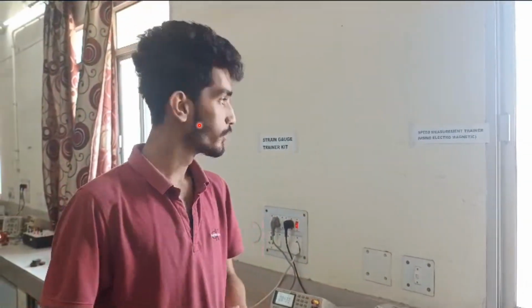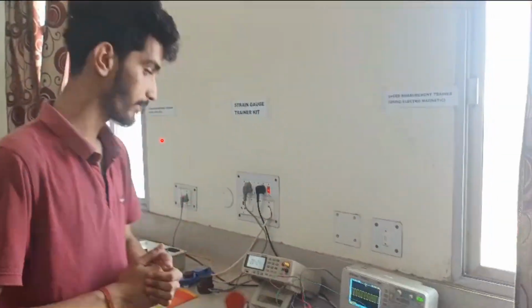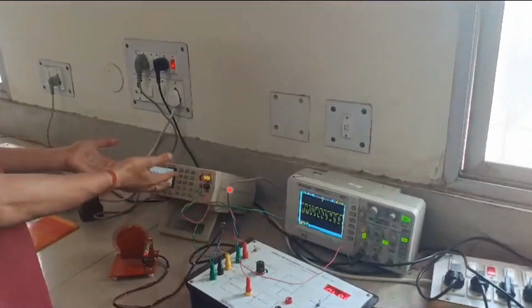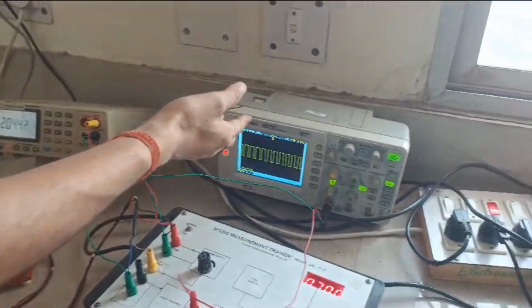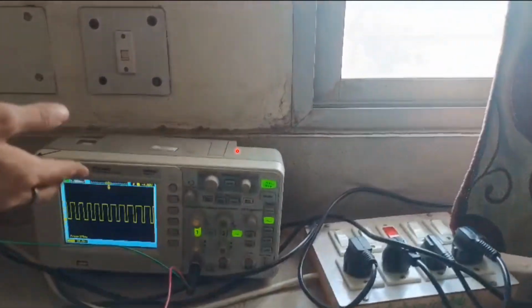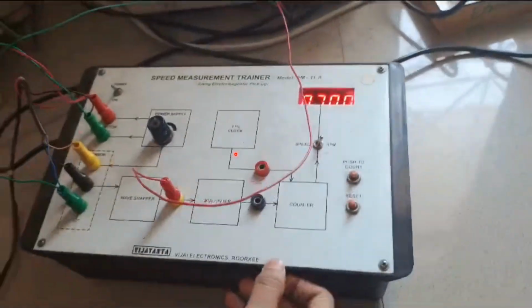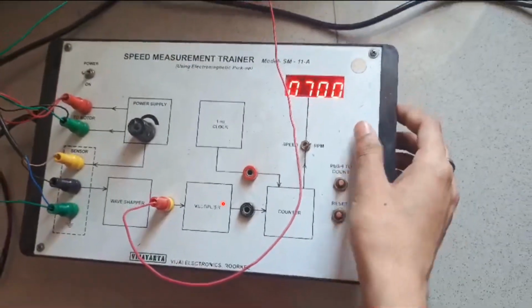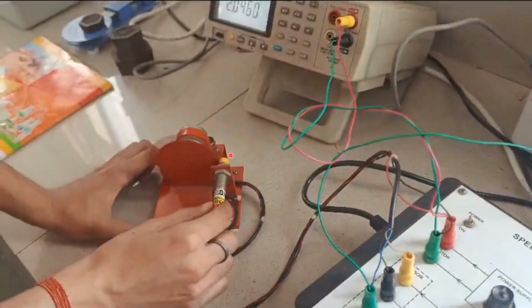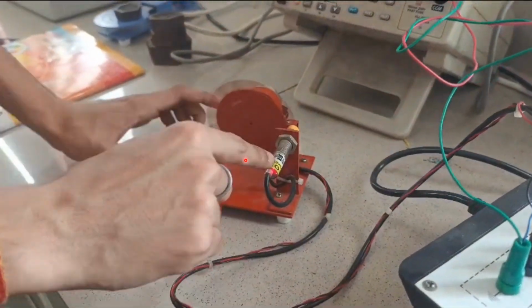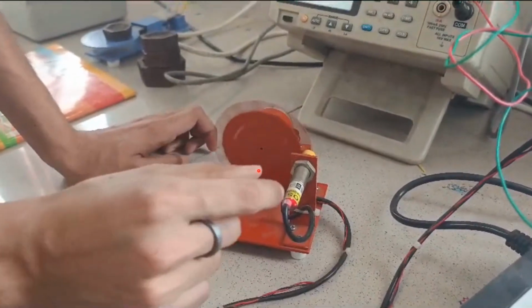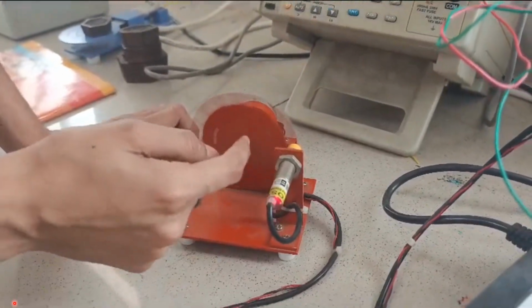This is the shaft with 15 slotted teeth. This is the electromagnetic pickup sensor. When it comes close to the shaft, in proximity to the shaft, it detects a higher signal, and when there is an air gap between two teeth of the shaft, it detects a low signal. Soft iron core. This is a ferromagnetic shaft.